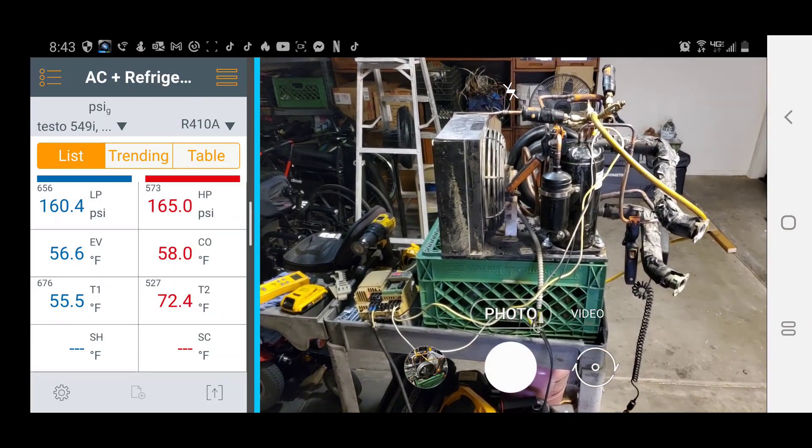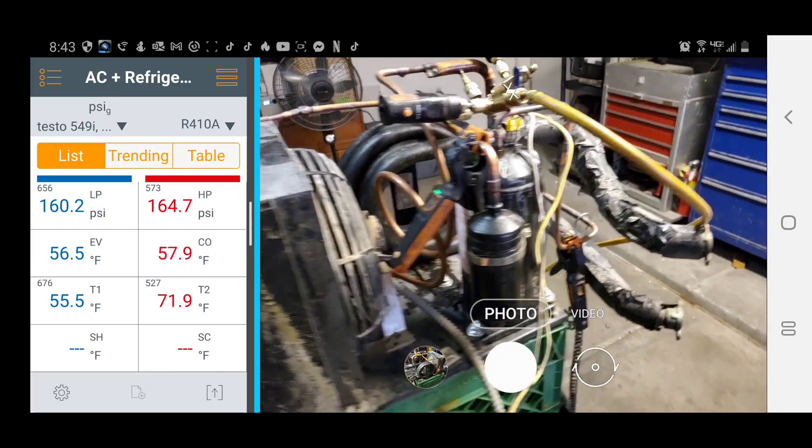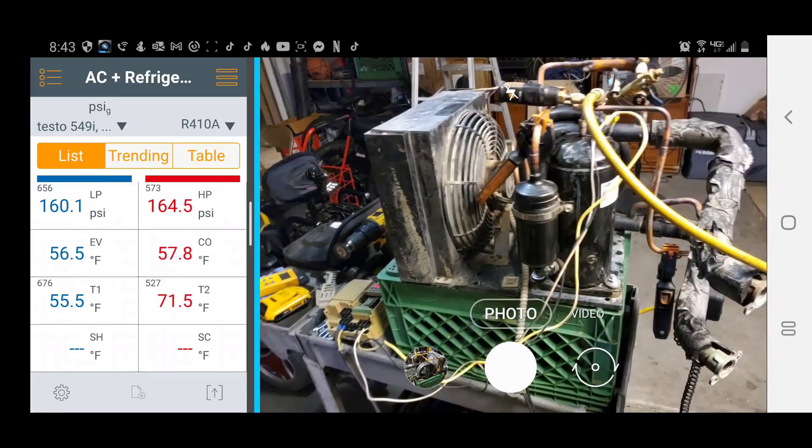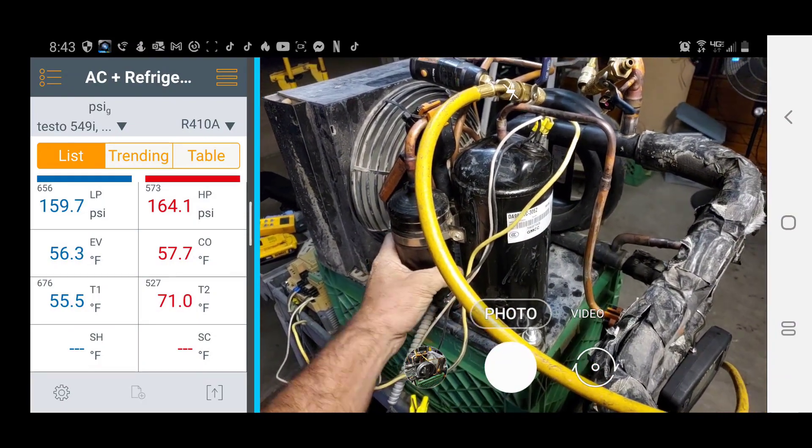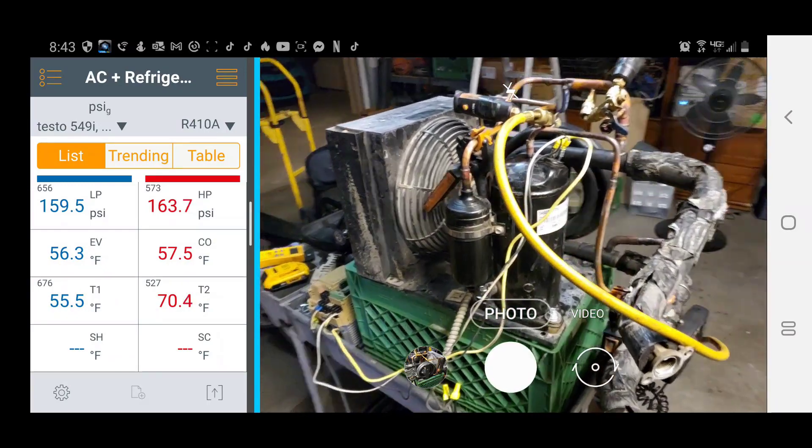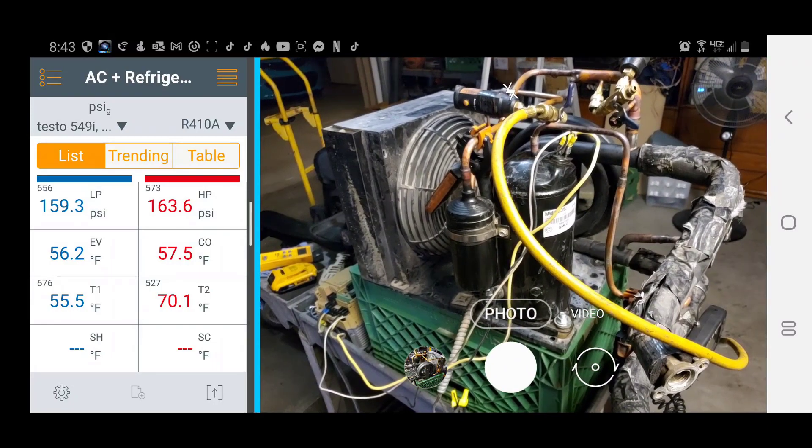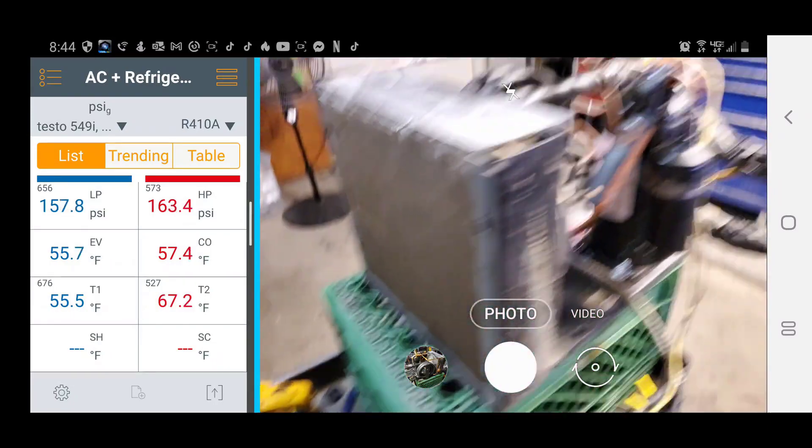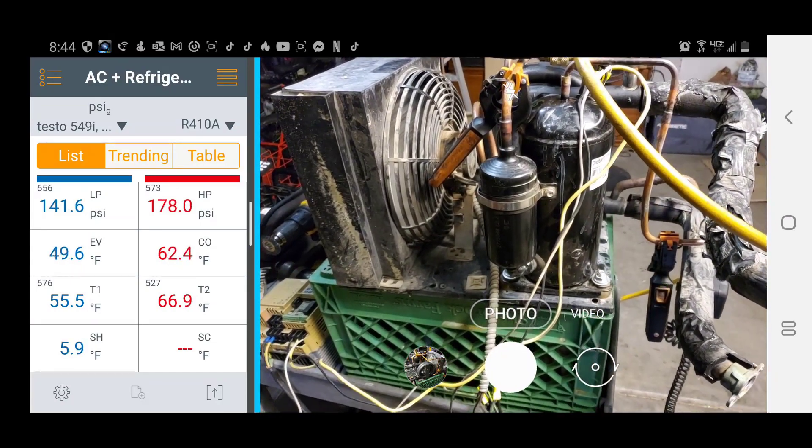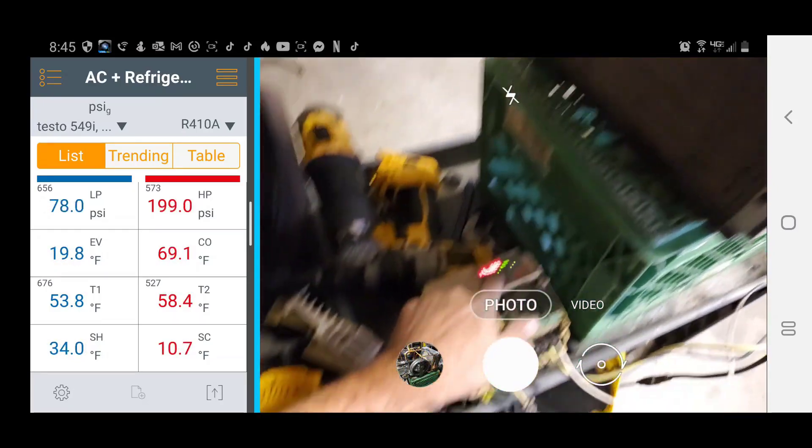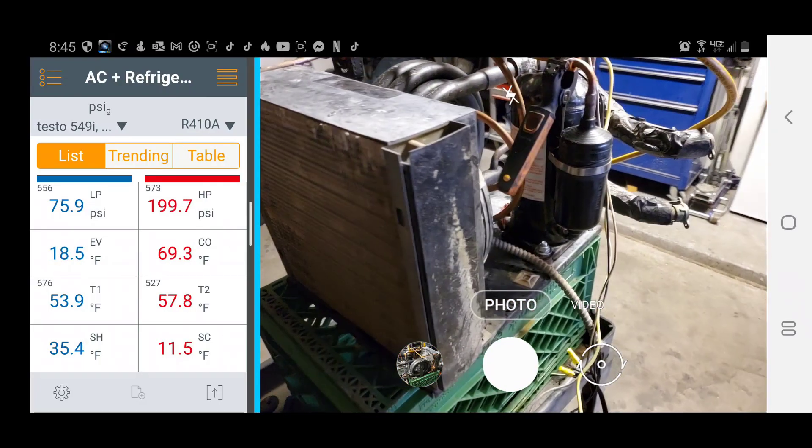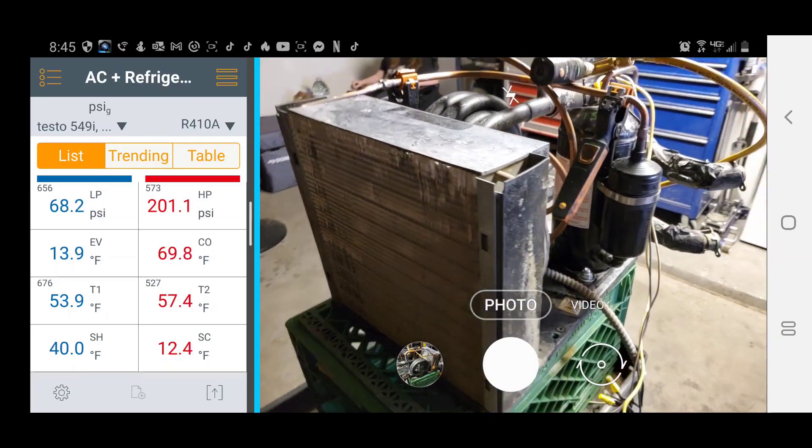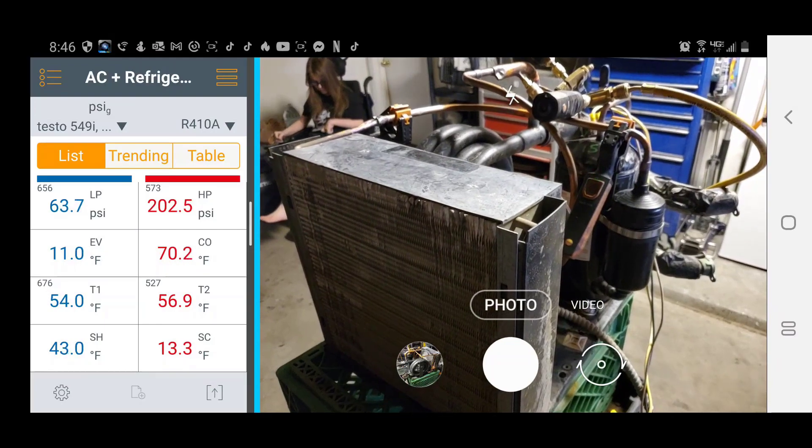Okay, well the compressor does run off the variable frequency drive. I've actually had it all the way up to 120 hertz, which is what it goes up to. But after a short operation it doesn't seem to be too happy. It does vibrate a little bit, which was the reason we replaced the compressor—it was from a complaint someone else diagnosed. When I ran the unit before I pulled out the compressor, it actually seemed to be working and it does pump. It's at 54 hertz, which is really slow for one of these.